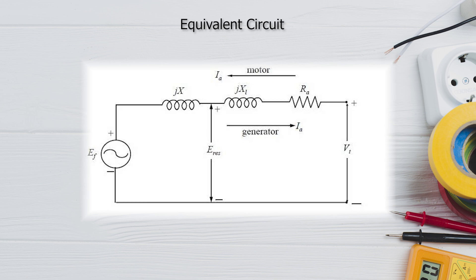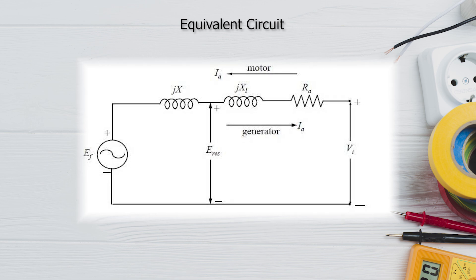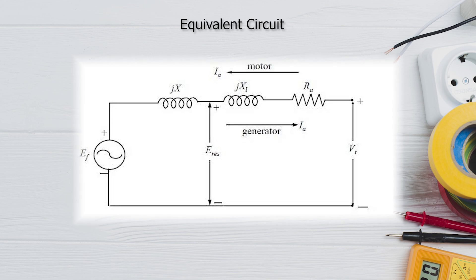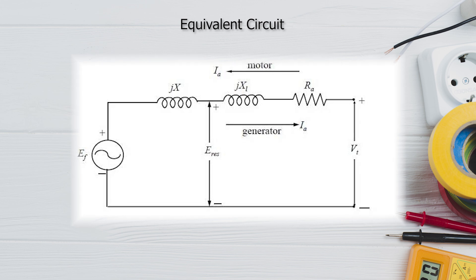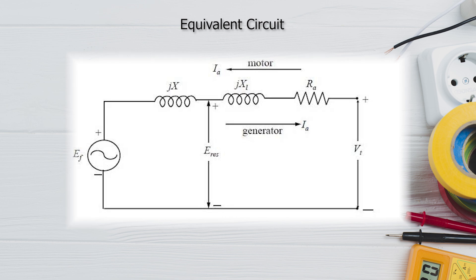In the equivalent circuit, we have EF — the induced EMF in the machine — then the armature reactance Jx, and then the armature reaction. Together, these reactances are combined and called the synchronous reactance. We also have the armature resistance connected. These three factors lead to some voltage drop, and the terminal voltage Vt will be slightly less than the generated EMF when current flows in the generator direction.